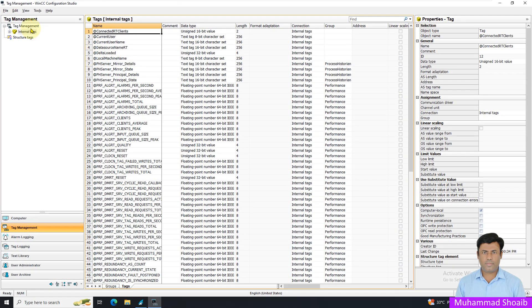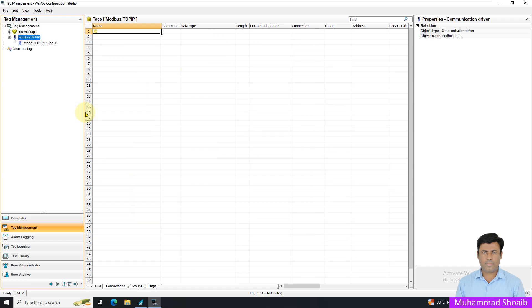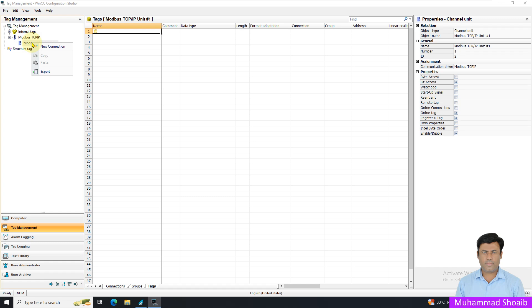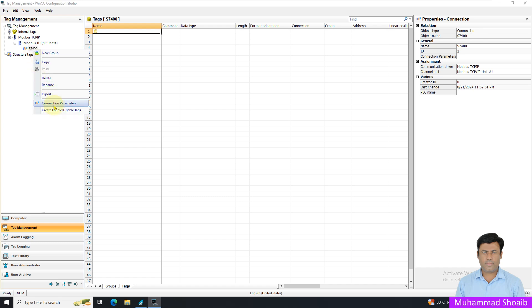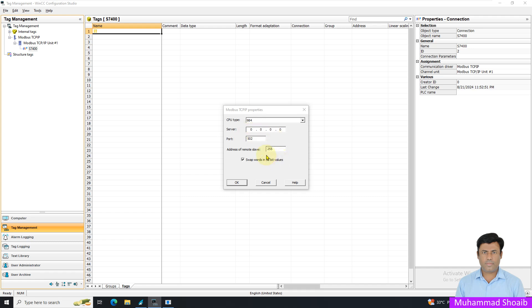To configure the communication protocol in WinCC, come to Tag Management, right-click and open. In the Tag Management upper area, right-click, add a new driver, and select Modbus TCP. Then right-click and add a new connection — put your PLC name, for example 'S7400'. Right-click and click Add Connection Parameter. Here you have to put the IP address, port number, and station address of your Modbus TCP server. For my server, the IP address is 192.168.0.142 and the port number is 502, which is the default Modbus port.